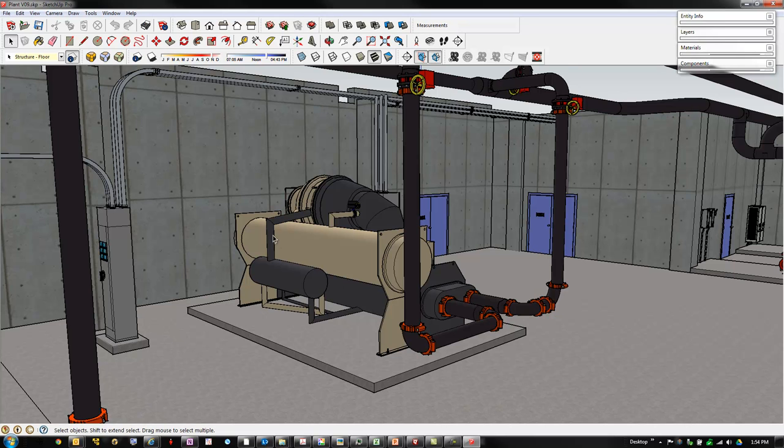So there has to be a way to reduce the pressure. And when you reduce the pressure, some of the refrigerant is going to flash off to a vapor anyway. So basically the economizer reduces the pressure in two steps. It takes some of that flash vapor and re-injects it back in between the compressor stages to improve the efficiency of the process. You're going to flash it to vapor anyway, so why not use it to help the process be more efficient? Then the remaining liquid flows through an orifice and flashes down to the pressure and temperature in the evaporator, and the process repeats.